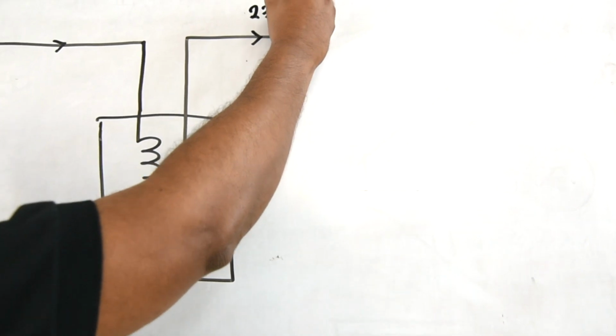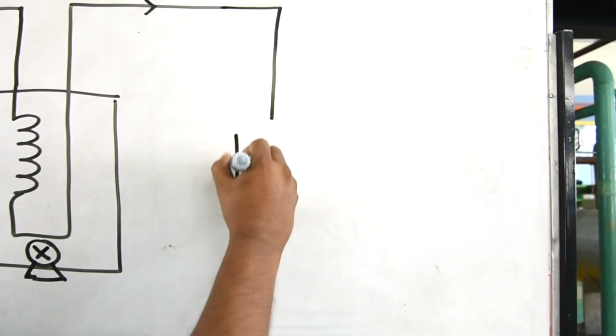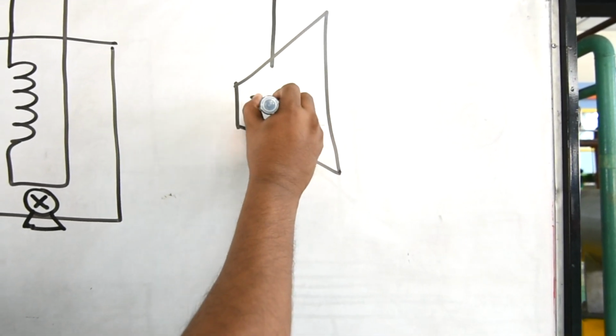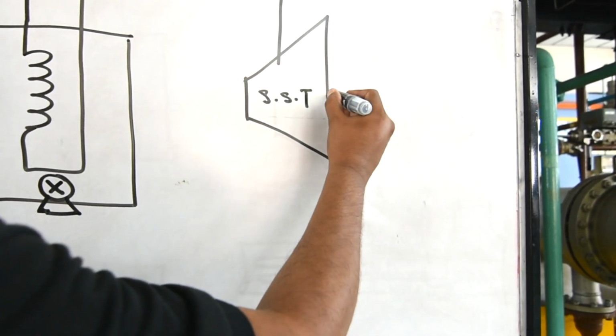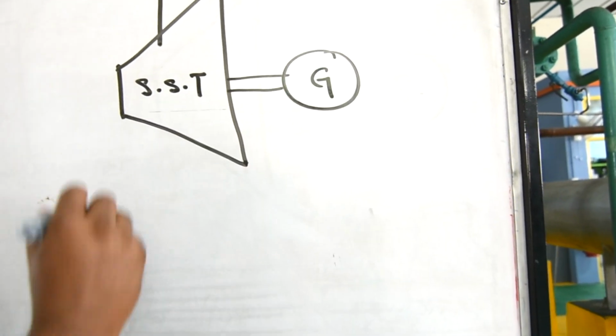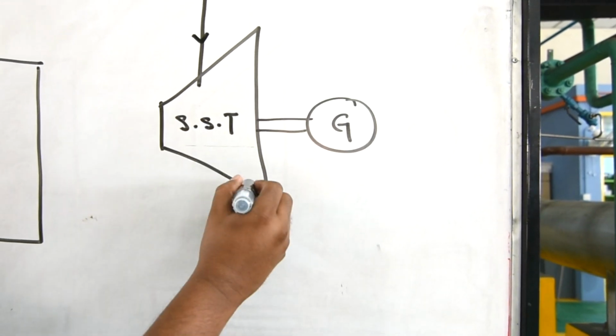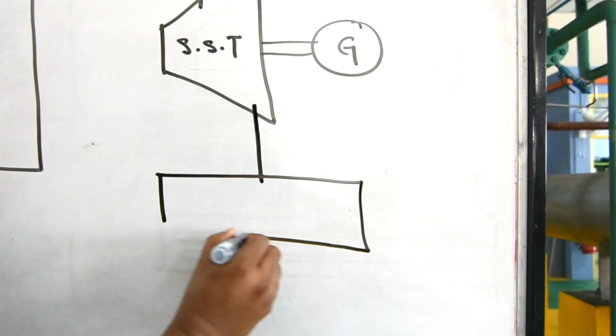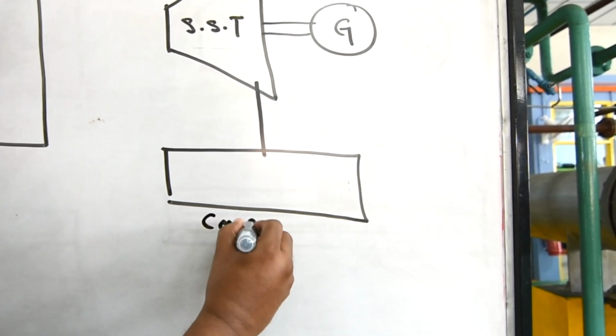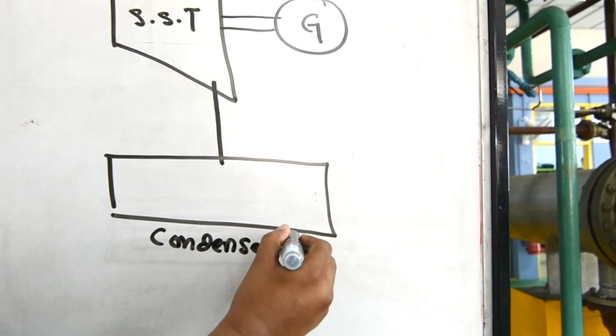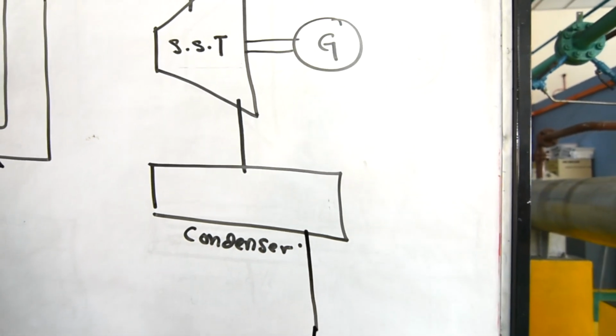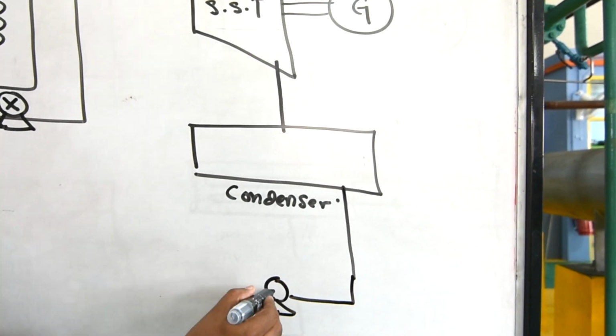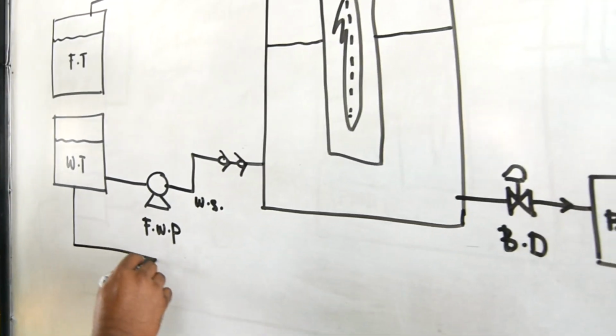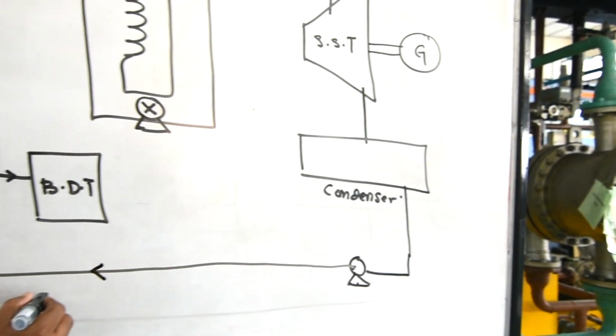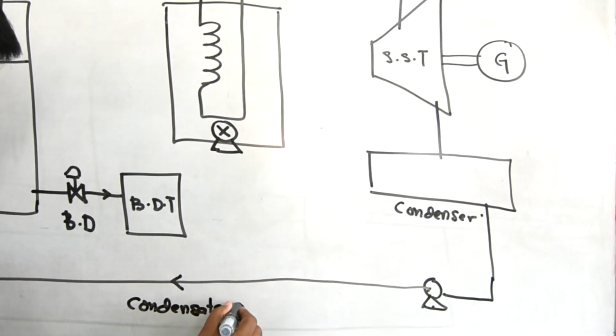And this superheated steam, which is up to 230 degrees Celsius, will drive a steam turbine. We have a single stage turbine. And this single stage turbine is connected to a genset. So once this superheated steam drives the turbine, we will have condensate steam which goes through a condenser. So this is a condenser. And the condensate steam will be pumped back by a condensate pump to the water tank. So we have a water tank, this condensate water will go back to it, so this is called the condensate water line.